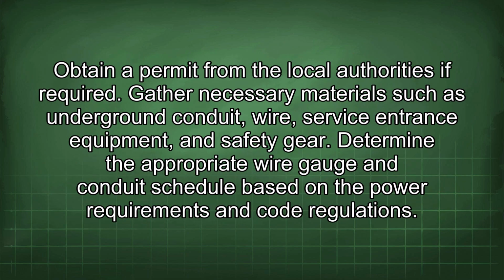Obtain a permit from the local authorities if required. Gather necessary materials such as underground conduit, wire, service entrance equipment, and safety gear. Determine the appropriate wire gauge and conduit schedule based on the power requirements and code regulations.